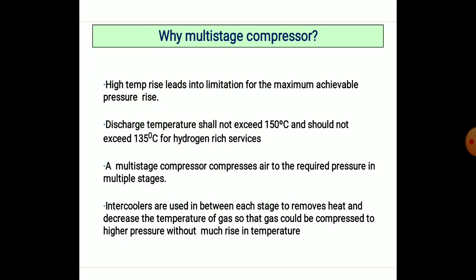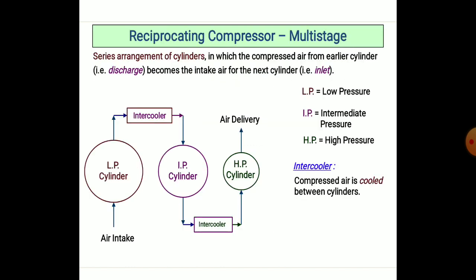A multi-staging compressor compresses air to the required pressure in multiple stages, and intercoolers are used between each stage to remove heat and decrease the temperature of the gas, so that the gas can be compressed to high pressure without much rise in temperature.